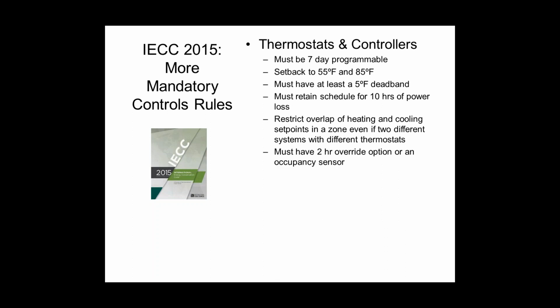You have to have the ability to override the thermostat for up to 2 hours. Someone walks up to the thermostat, and instead of putting it in hold mode, if they push the buttons to increase or decrease the set point, it should override for just 2 hours, or give them the option of picking how many hours they want to override it for. Or you can put a motion occupancy type sensor in there and do it that way.